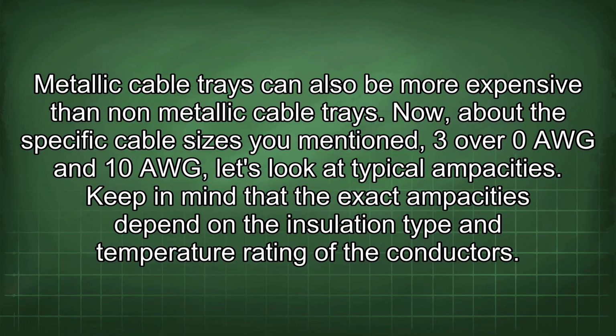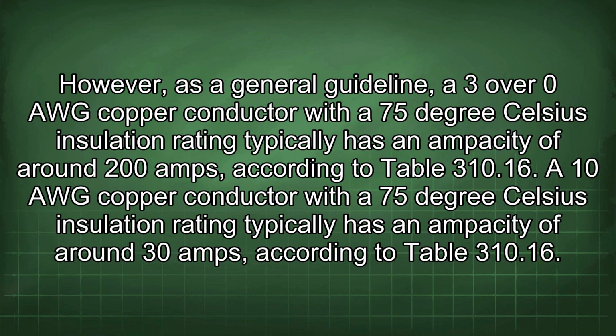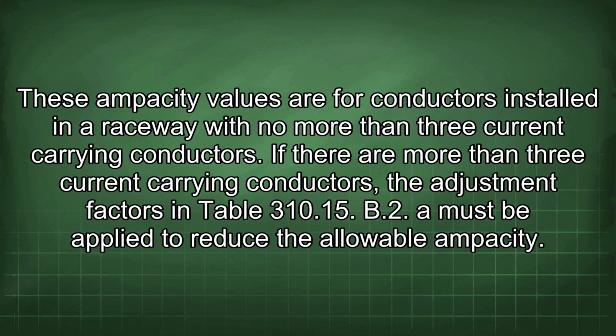Keep in mind that the exact ampacities depend on the insulation type and temperature rating of the conductors. However, as a general guideline, a 3/0 AWG copper conductor with a 75 degrees Celsius insulation rating typically has an ampacity of around 200 amps, according to table 310.16. A 10 AWG copper conductor with a 75 degrees Celsius insulation rating typically has an ampacity of around 30 amps, according to table 310.16.